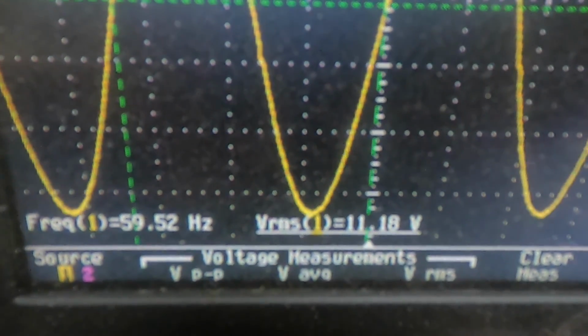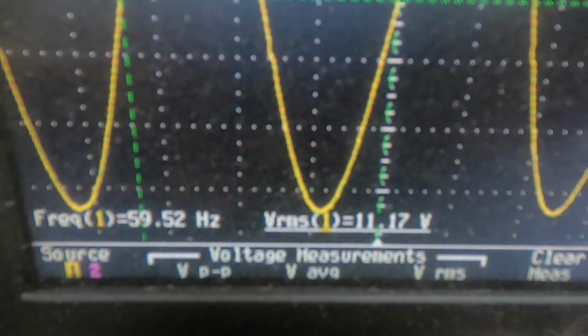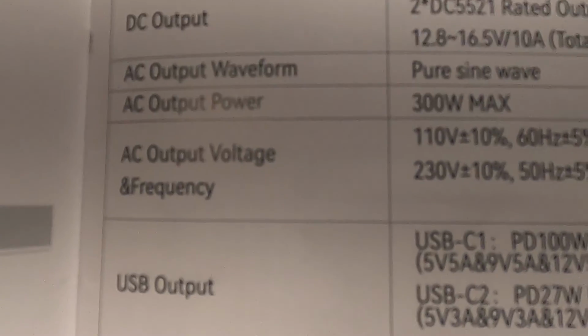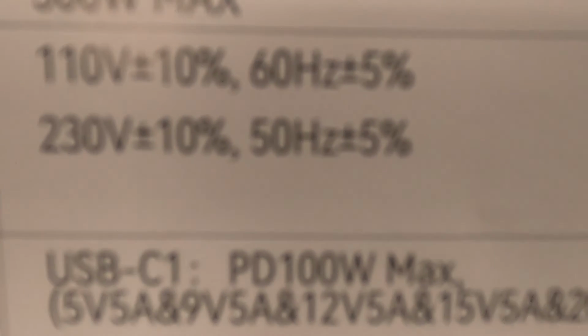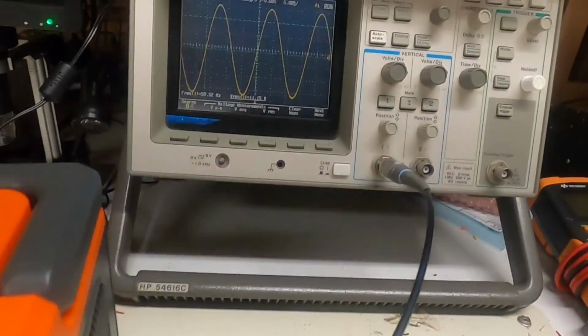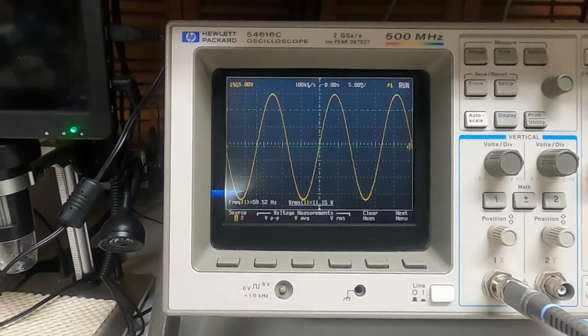So that would be 111.7 volts. If we look at the specification sheet, the AC output voltage is 110 volts plus or minus 10%. So reading 111.9 is well within the specifications. And the 60 hertz plus or minus 5%, again that is within spec. So as far as the AC output goes, that's pretty nice.